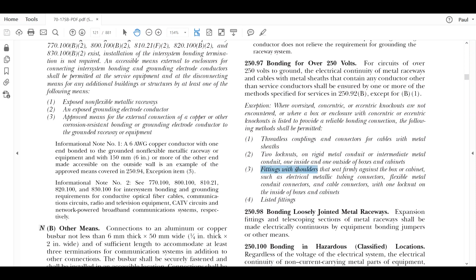I can use fittings with shoulders that seat firmly against the box or cabinet with an electrical metallic tubing connector or flexible metal conduit connectors. Okay, and we got to have 1 lock nut on the inside. Then that's going to be okay. No problem. There's enough surface area connection. It's got a flat shoulder. Most all of those FMC connectors do. And of course, lastly, if it is a listed fitting for that type of wiring method, then it is okay as well to make that connection.